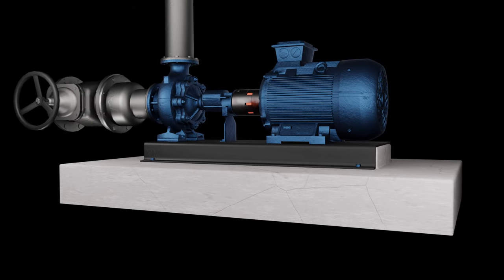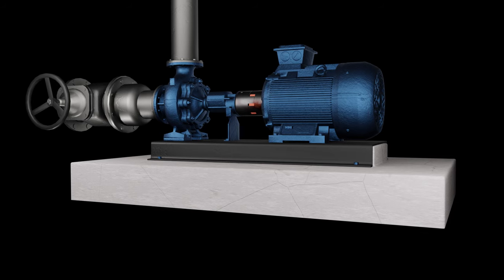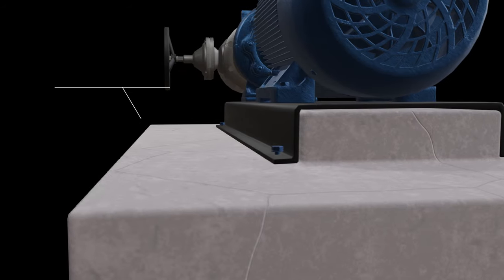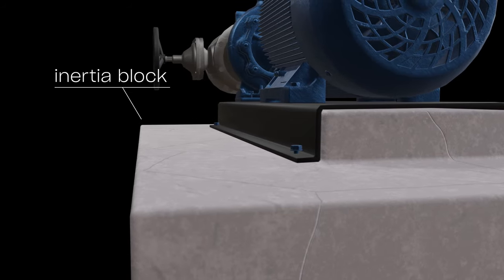A visual inspection should start at the bottom of the machine, where inertia blocks or bases provide a solid flat mounting surface for the machine.